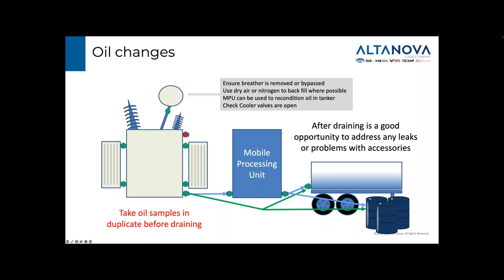When it comes to oil changes, oil will usually be removed into drums or a tanker. This can be achieved with or without a mobile processing unit. However, better oil drainage and hot oil flushing can be achieved with a mobile processing unit to more effectively remove the residual oil from the windings and the floor of the transformer. Ensure the breather is removed for this process to prevent its damage, and where possible, backfill with dry air or nitrogen to minimize moisture ingress. If the transformer has any leaks, gaskets, or other accessory issues, now is a good time to get these fixed. Remember to take oil samples before and after the work in duplicate.